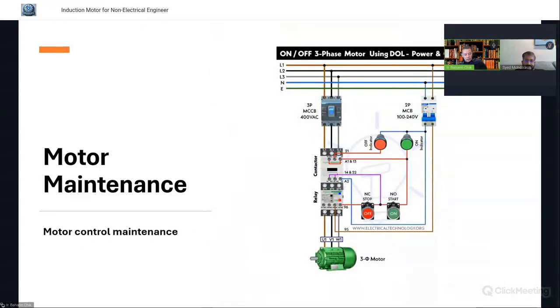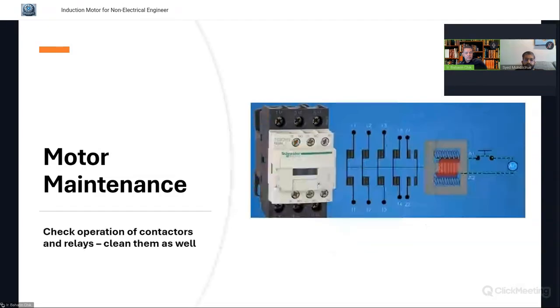And not only the motor itself, you need to also concentrate on the motor control center for the maintenance. You clean all this dust that accumulated in the contactor or MCCB. And then check also the operation of the contactors. Make sure that the solenoids for this contactor are working fine. Occasionally or regularly check this, for the good contact.